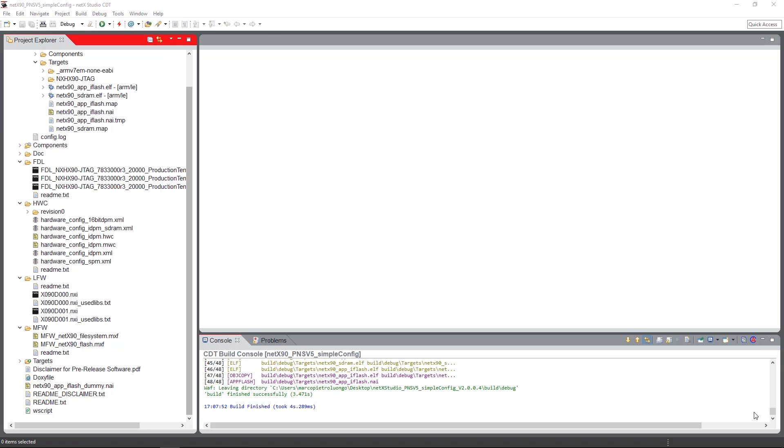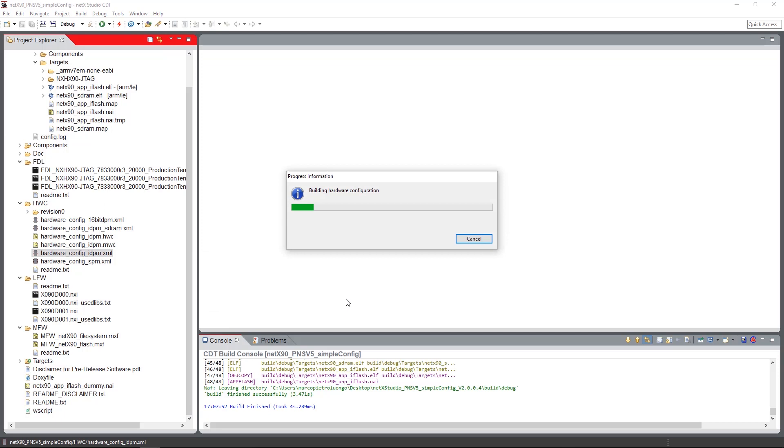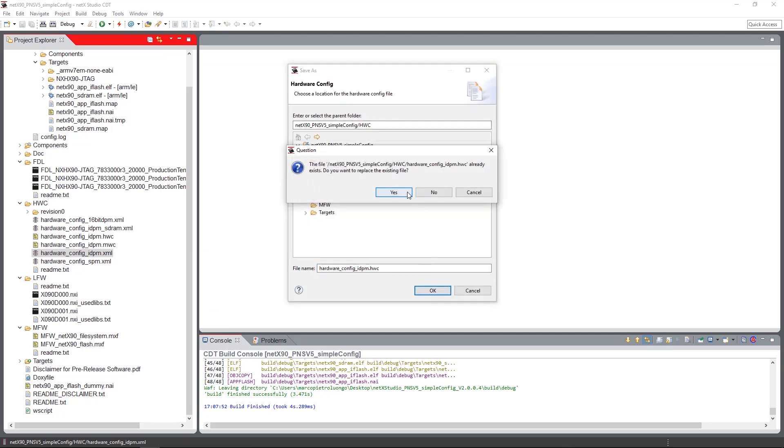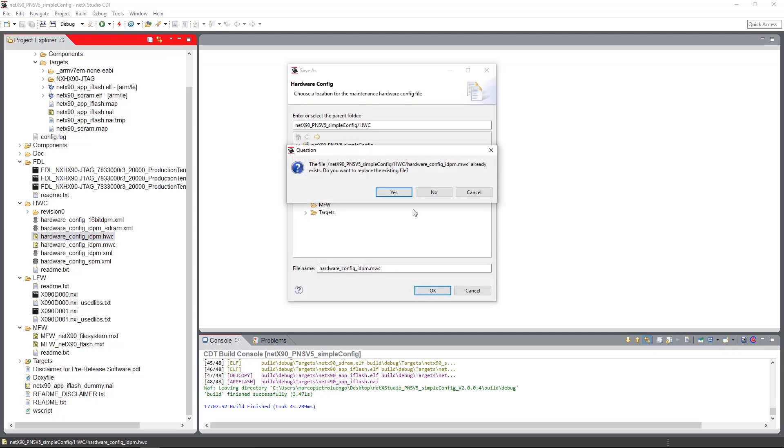At first we will flash the communication side images. On the communication side, there is first the hardware configuration. We have to generate the hardware configuration by right-clicking on the XML file and selecting build hardware configuration. Then we will generate the hardware configuration itself and also a so-called maintenance hardware configuration, MWC.